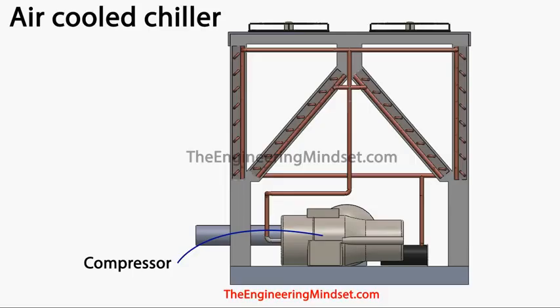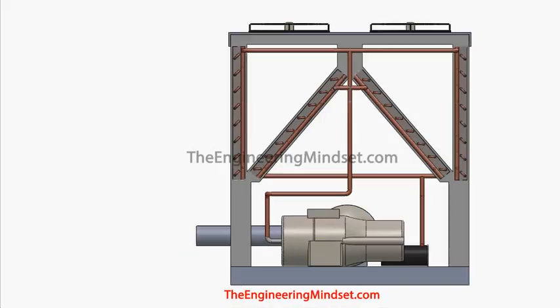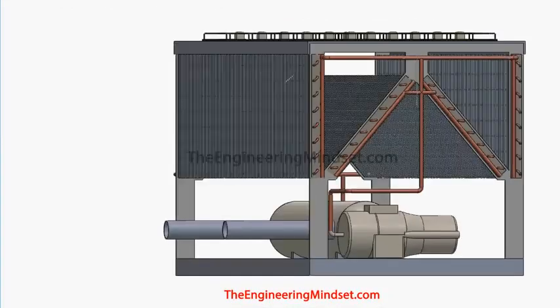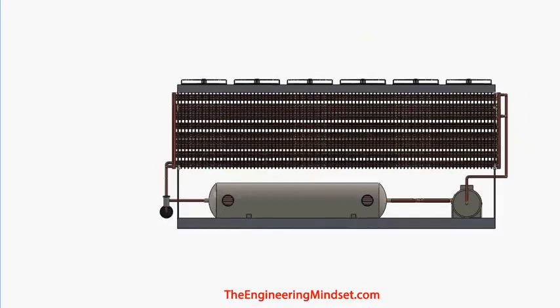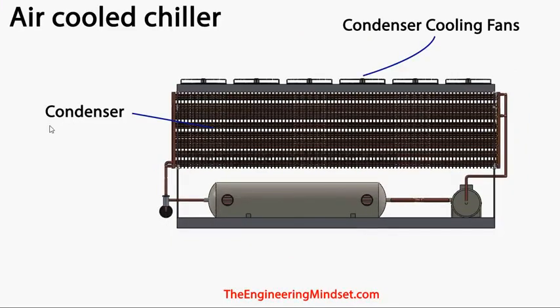But anyway, the compressor pushes and forces the refrigerant off through these tubes and off into the headers here, and off towards the condenser. So these are all the condensers, we'll see that in just a minute. The refrigerant will leave here as a high pressure, high temperature, superheated vapor. And if we then change the view of this one again, you can see that this part here is known as the condenser.